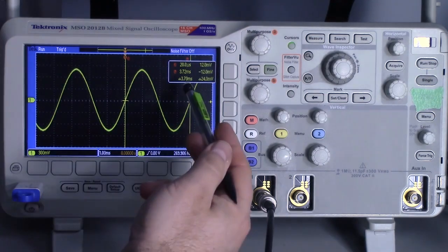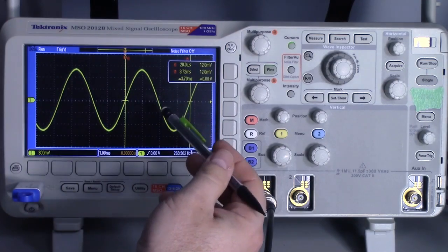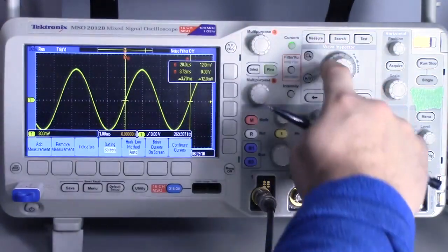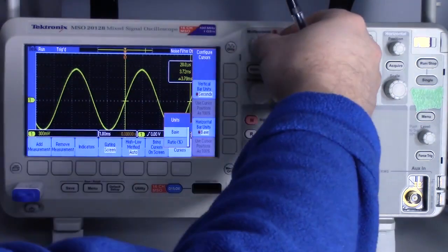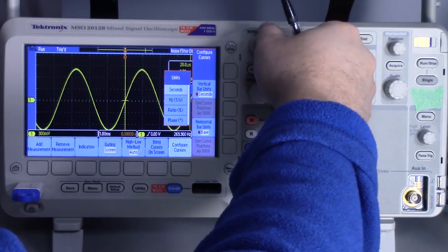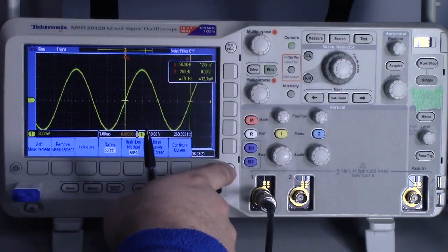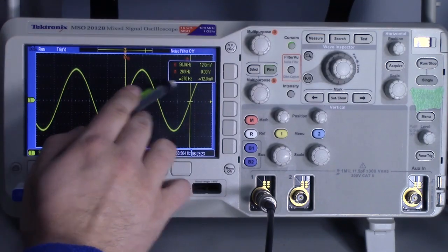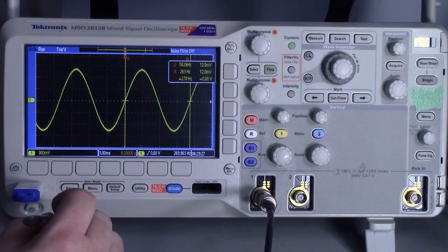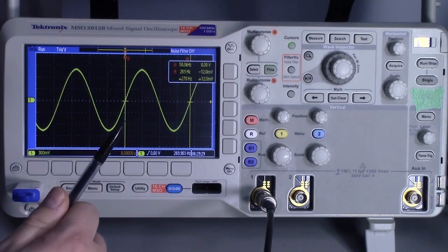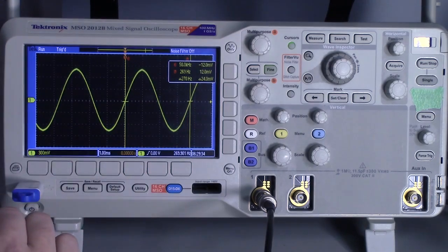With this oscilloscope, you can change the information that's displayed for the cursors. To do that, we go up to Measure and Configure Cursors, and we want to change the channel multi-purpose A to Hertz. Menu off, menu off. Now it tells us more directly: it's 270 Hertz, and the function generator is putting out 269.9. Down here, it also tells you a little more precisely.